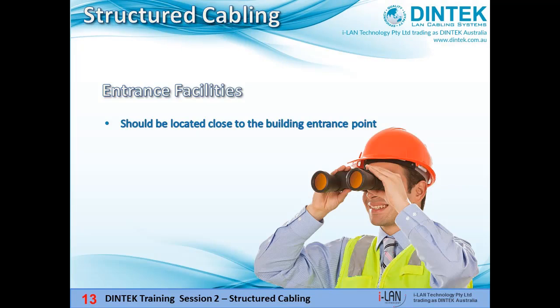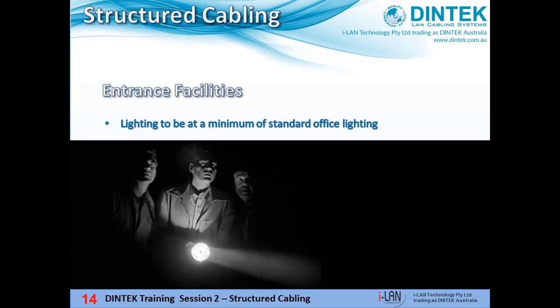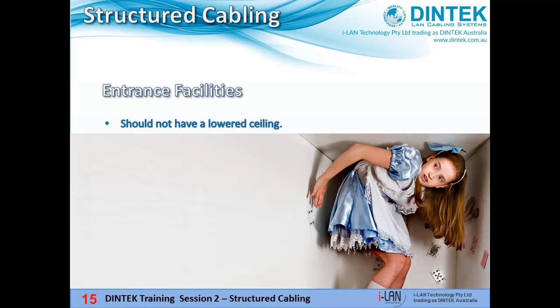There are several technical and OH&S requirements for entrance facilities. They should be located close to the building entrance point. If the lead-in cable outside ever needs to be replaced or upgraded, you don't want to be running cable through cavities that only existed while the building was being constructed. We also need to consider that conduits and tunnels, both phone carrier and private, when below ground can get gases in them including car exhaust fumes — you don't want that gathering in the middle of the building. They should have adequate lighting, and the ceiling should be standard height so the majority of people can stand up in them.